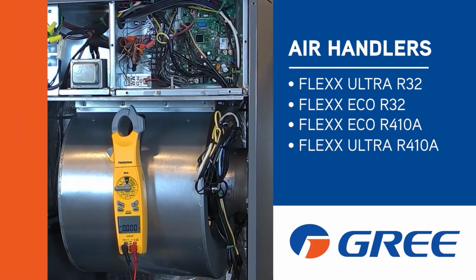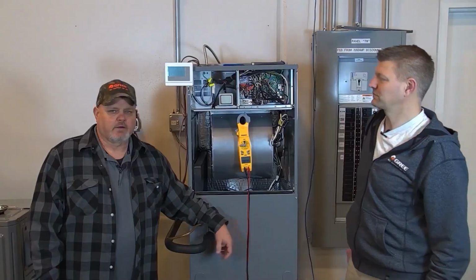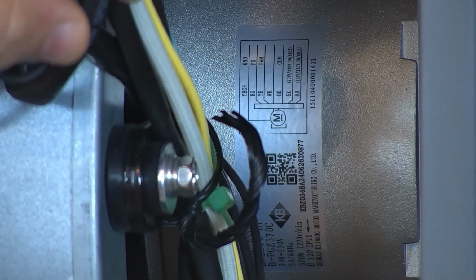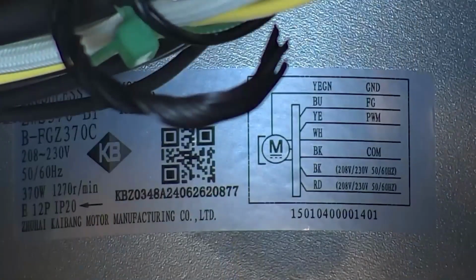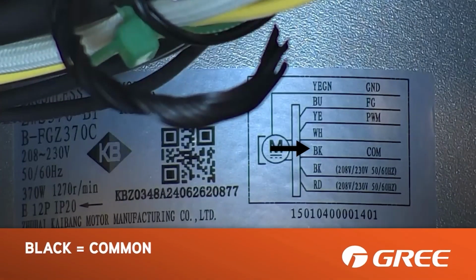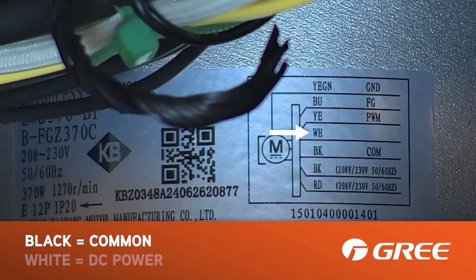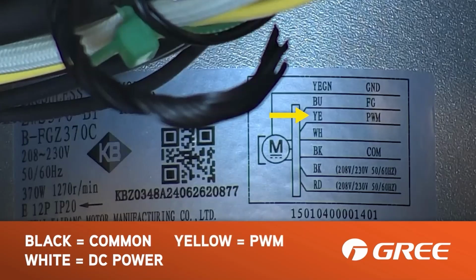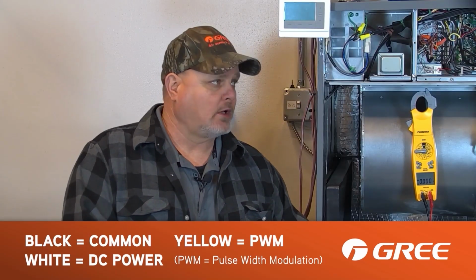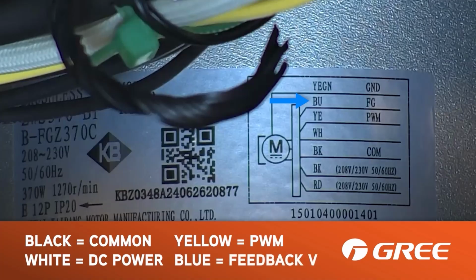For troubleshooting, let's look at the motor wiring diagram, shown here on the label on the motor itself. You'll see a black wire, that's your common. A white wire, that's your DC power. And a yellow wire, which is your PWM, the pulse width modulation signal that tells the motor to come on. Then the FG wire, the blue wire, is your feedback voltage. You won't get a voltage on feedback unless the motor is actually running, so we don't really care about that for troubleshooting whether the motor runs.